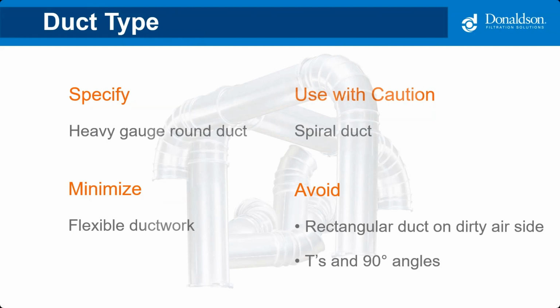Be aware that although flexible duct allows employees to modify the physical hood location to fit the process, it requires significantly more energy than traditional hard ducting. So if you are going to specify flexible ducting, we recommend minimizing it as much as possible. And you want to avoid branch entries with T's and hard 90-degree angles.